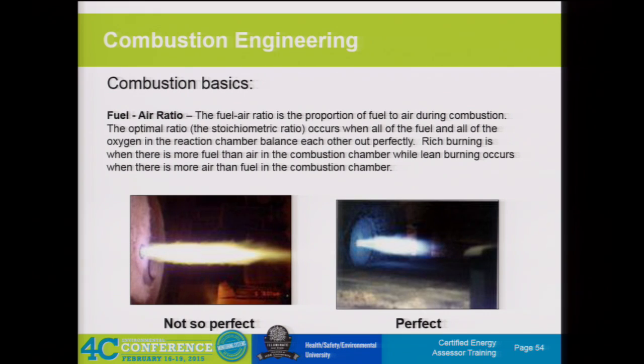Those are all inherent design components to the burner or the boiler. Usually the main tool we have to maximize efficiency is the adjustment of our air. The air-to-fuel ratio becomes very important in normal operations of the boiler. A lot of units will have online monitoring for stack O2, or in some cases stack CO as well, to give the operator some operational parameters and real-time indication on how a unit is performing. When we do the boiler tuning, inspecting the flame pattern is one part of that boiler tune-up that we're looking at.